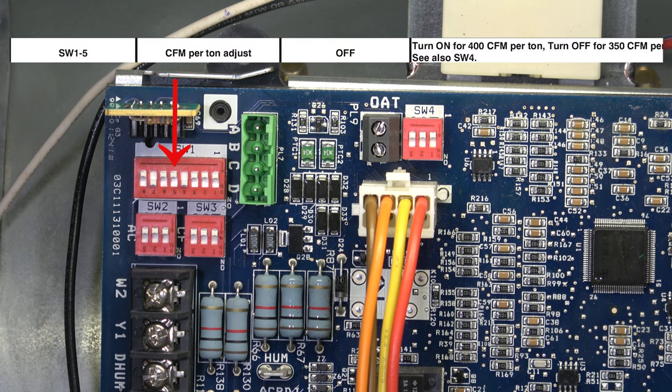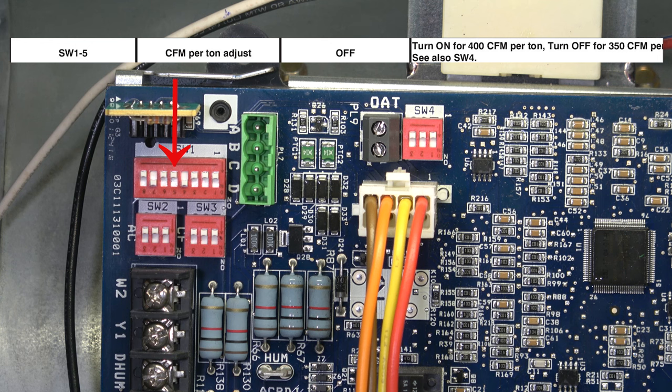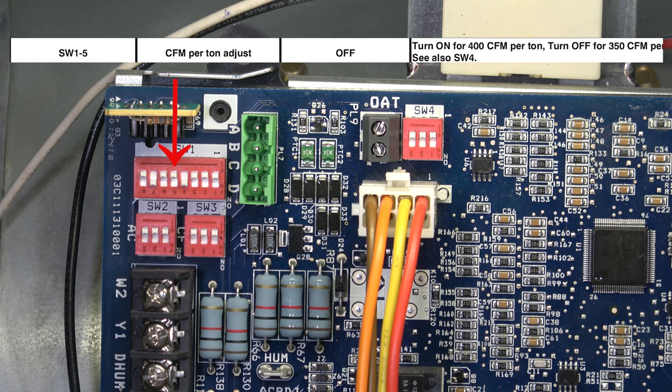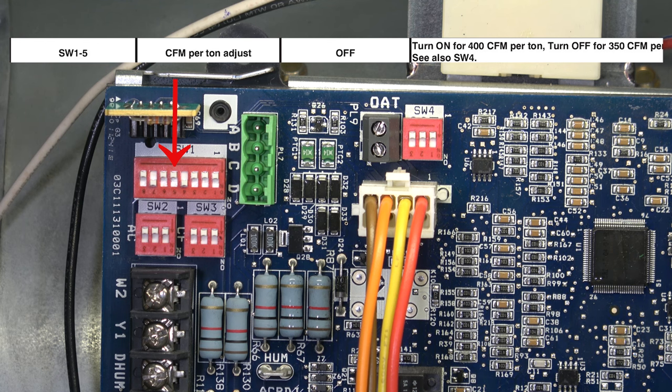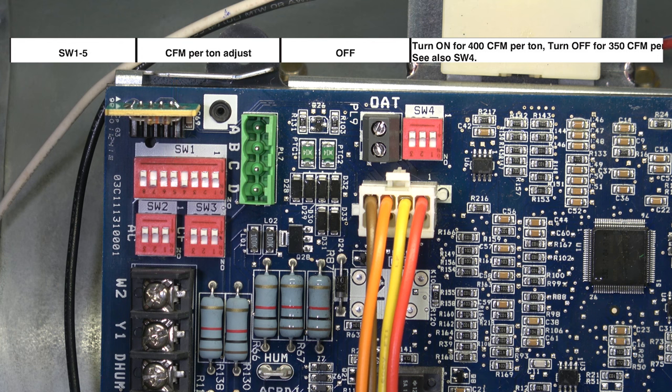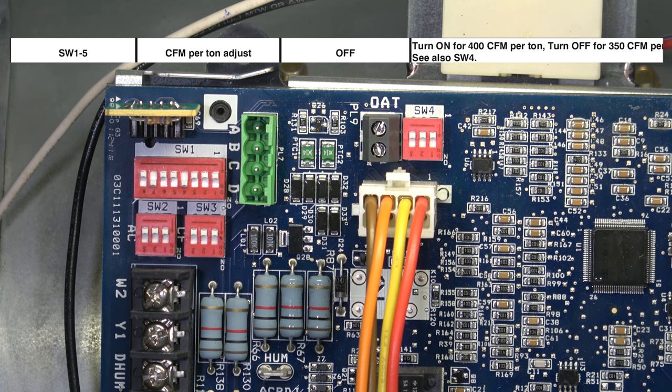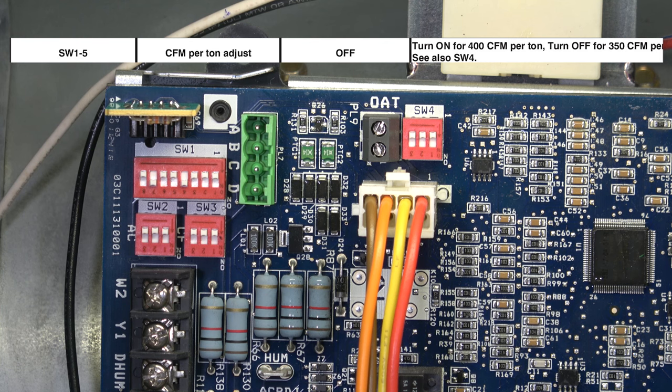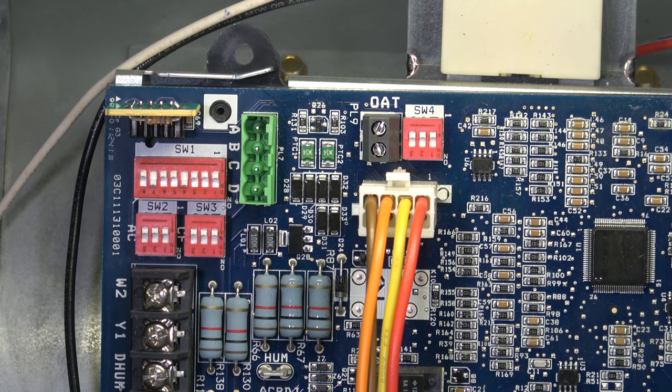Moving to the next, SW1 number five is the CFM per ton adjustment. It comes in the off position. The off position for the factory setting is 350 CFM per ton. If you turn that switch to on, it would be 400 CFM per ton.